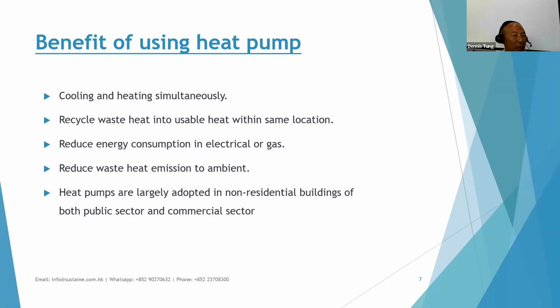So the benefit of using a heat pump is that it can provide cooling and heating simultaneously. The most important is that it locally recycles the waste heat into usable heat within the same location. So we don't need a power network to transfer the heat, the energy, from one location to another, and also no need for transportation, which also generates CO2 emissions. At the same time, we can reduce energy consumption in the building, both electrical and gas, and also reduce the waste heat emission to our ambient.